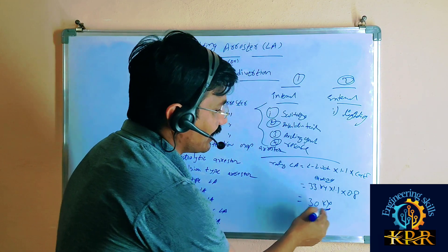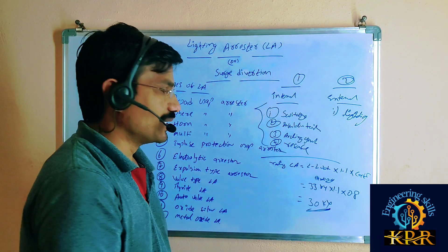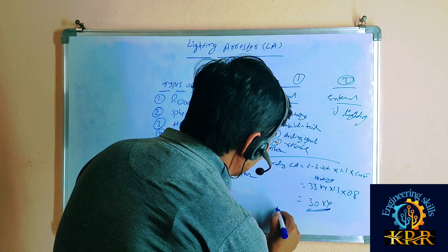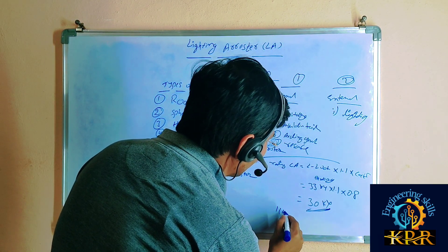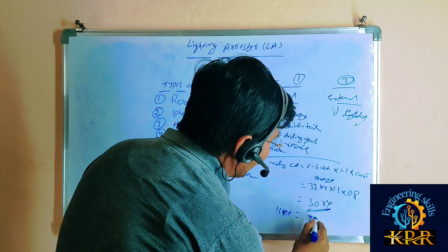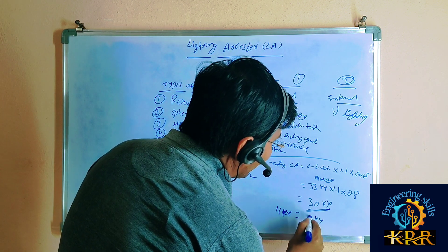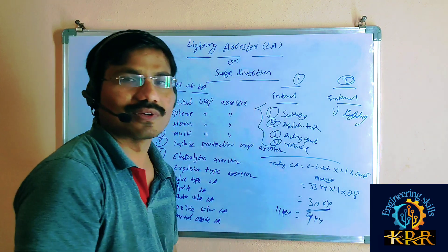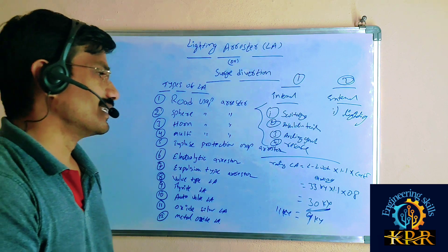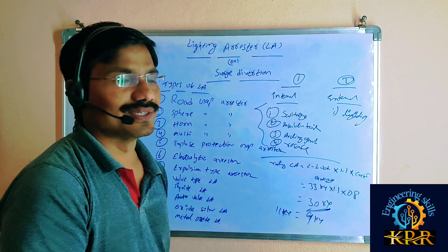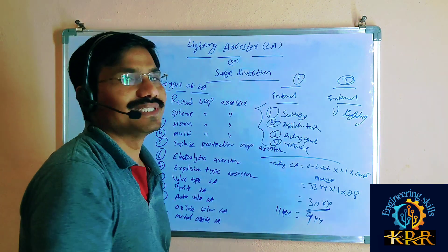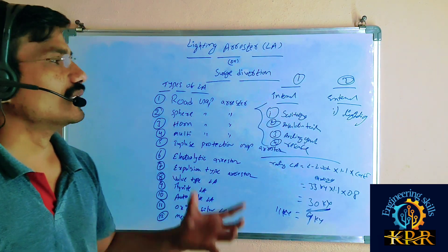Similarly, if the operating voltage is 11 kV, then a 9 kV lightning arrestor is required. These lightning arrestors are mainly used in transformer areas or substations.